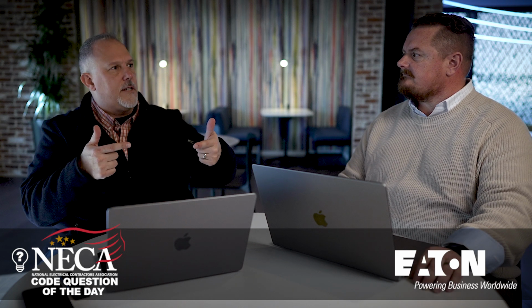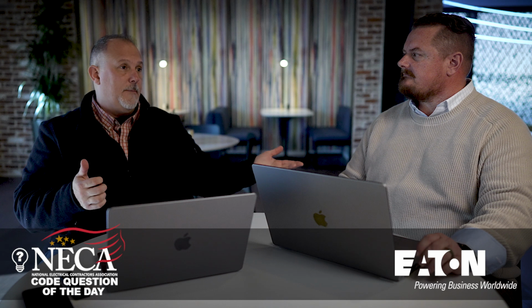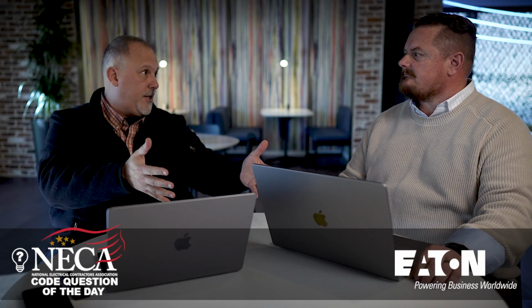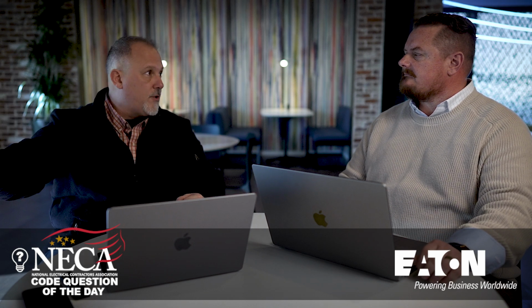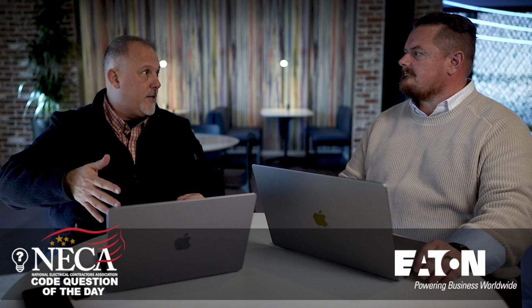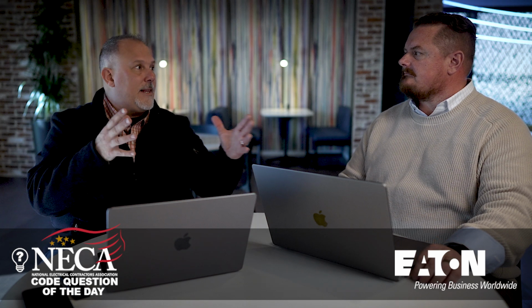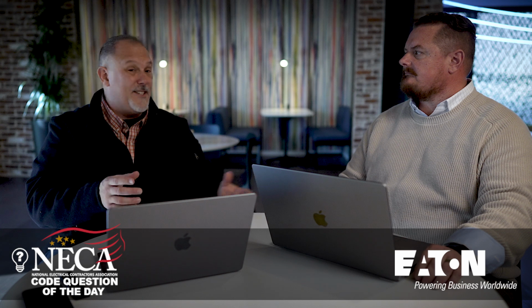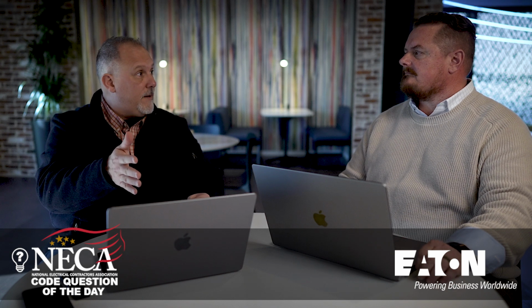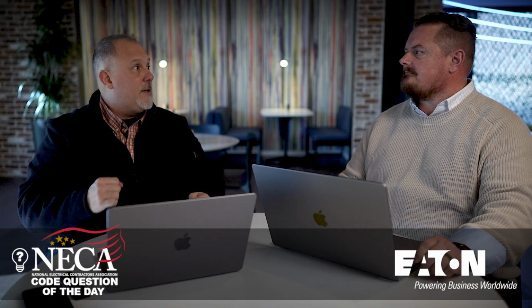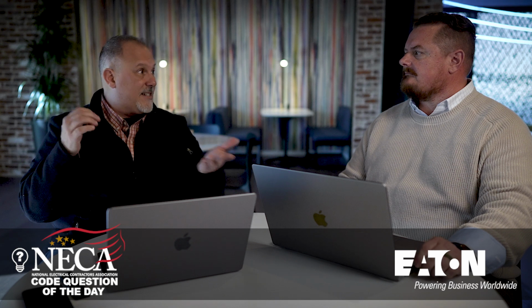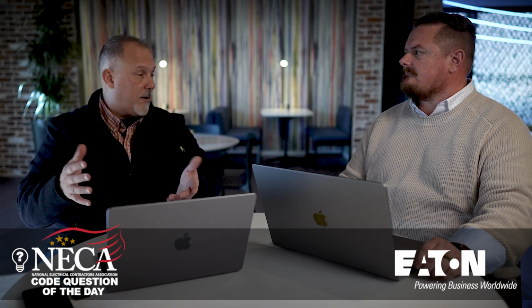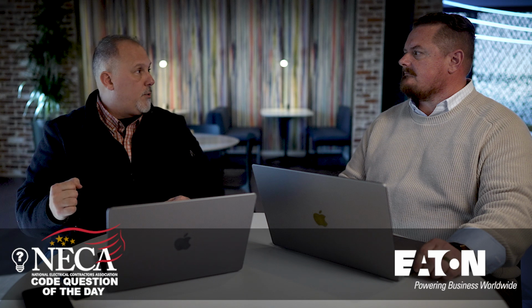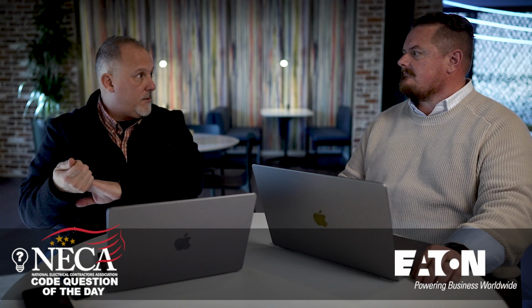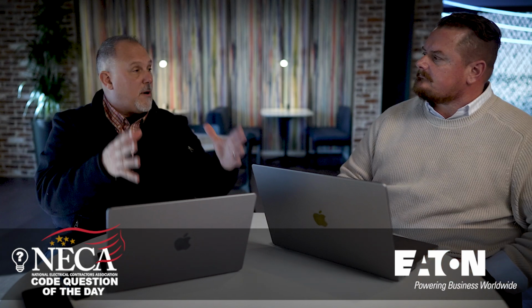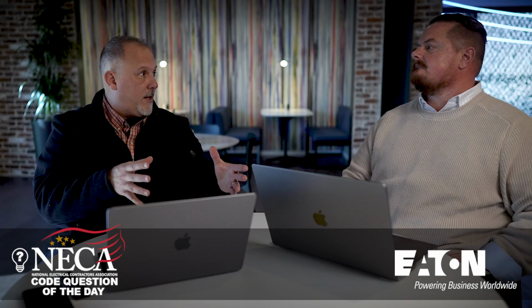So my thought process was, and what I told him, I said, look, because of the equipment, you can't change it. You're either going to have to put a 1-to-1 transformer out in front of it, to lower that fault current, temporarily, because he had the equipment down at the time and he wanted to re-energize it. I said, you could put a fusible disconnect in front of it that increases the likelihood you're going to establish an electrically safe work condition. So anybody who's going to work on it, they can reach over, pull the handle, lock and tag it out, okay? And if there's a problem in it, the incident energy is going to be very low.